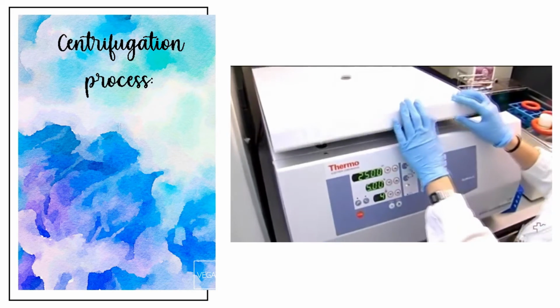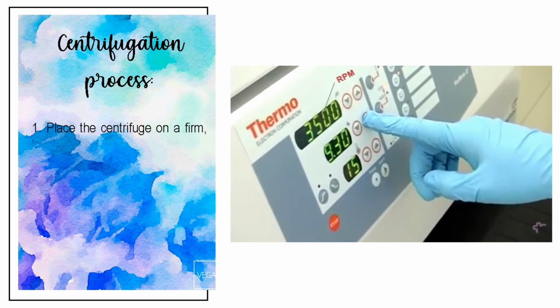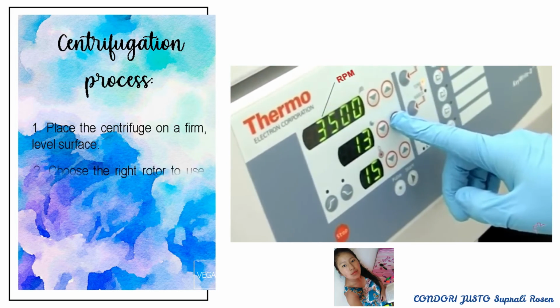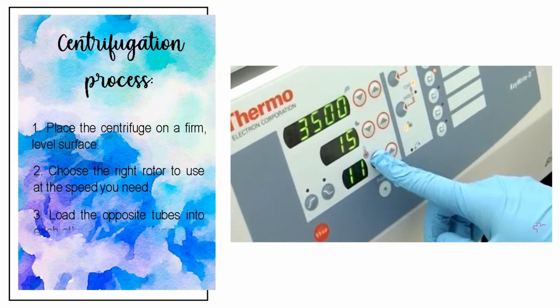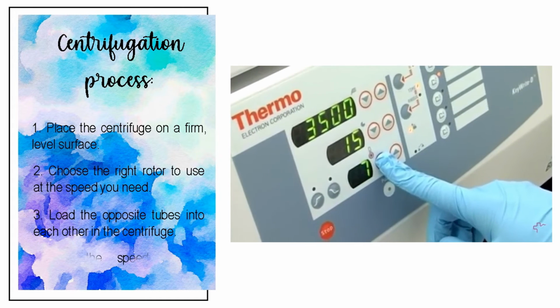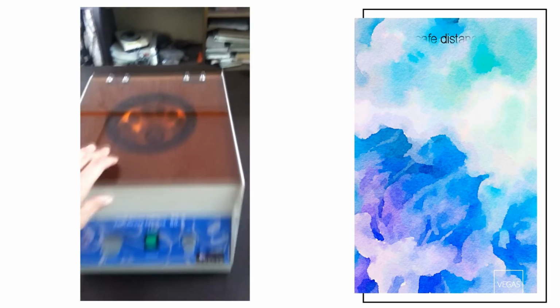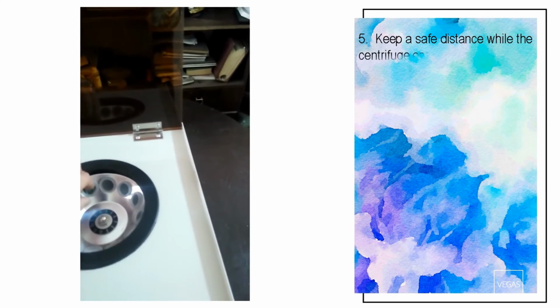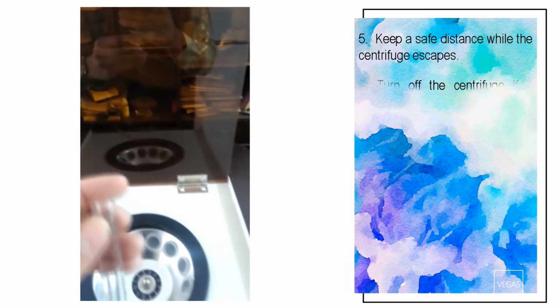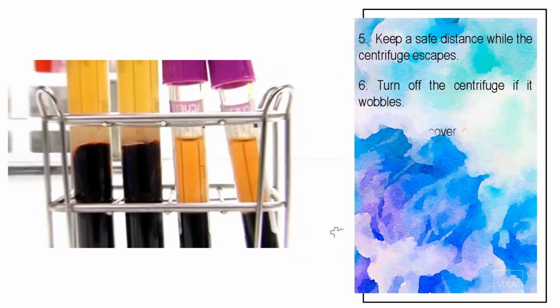Centrifugation process. First, place the centrifuge on a level surface. Use the right rotor for the speed you need. Load the balanced tubes opposite each other in the centrifuge. Enter the speed of the centrifuge. Keep a safe distance while the centrifuge operates. Open the cover only after the rotor has come to a complete stop.